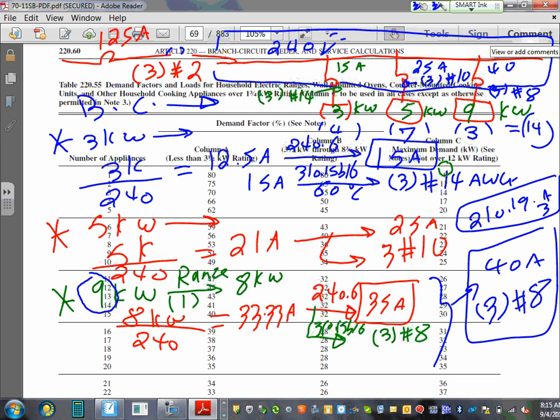So here's a range, 9 kW range. Under one of them, give me 8 kW right in here. Can you guys see it? Right here. Then I start doing the branch circuit calculation for the 8 kW. I did them, 33 came up. I go size my overcurrent protection device and size my conductors, because that's what we do. Overcurrent protection device, conductor. Okay, so that will give me number 8 from Table 310.15(B)(16) under which column?